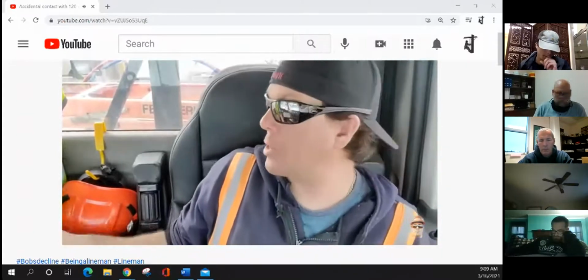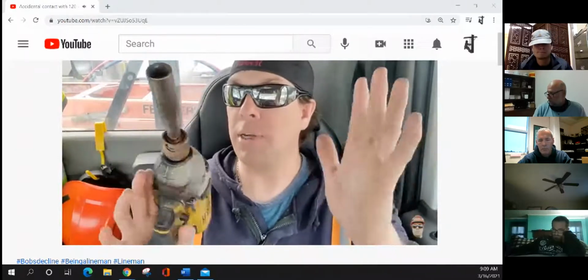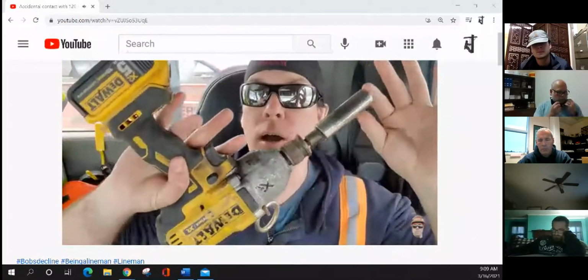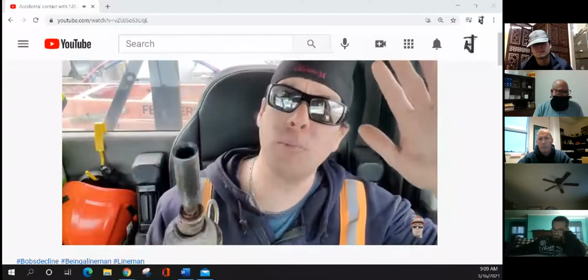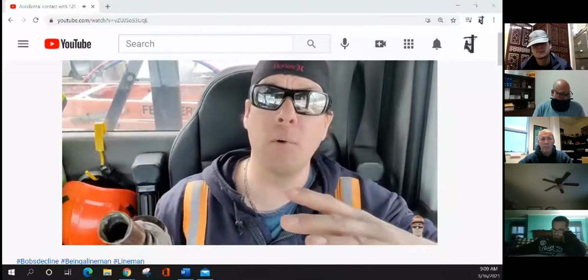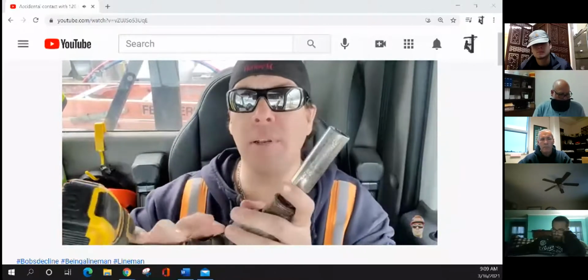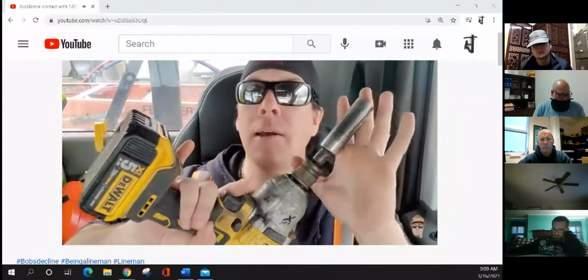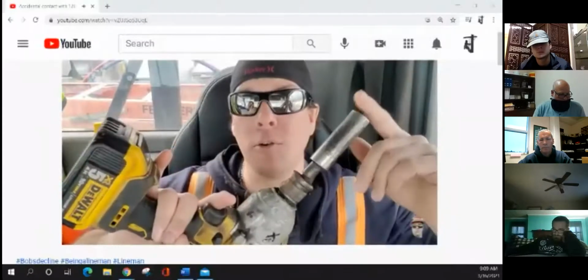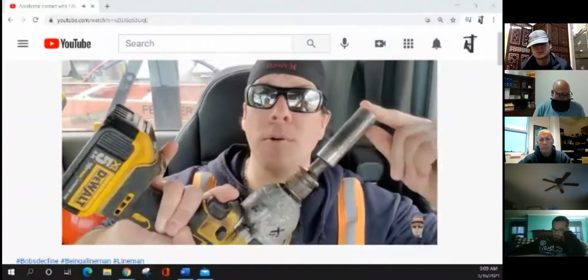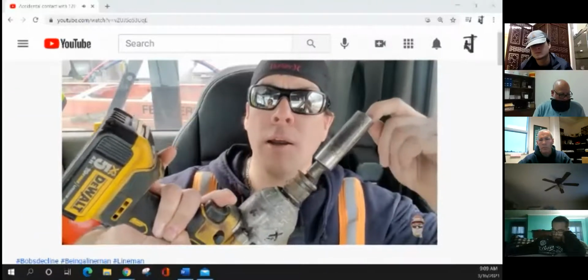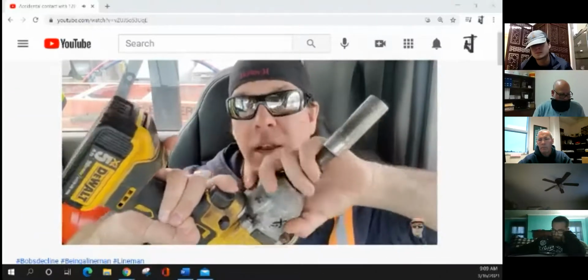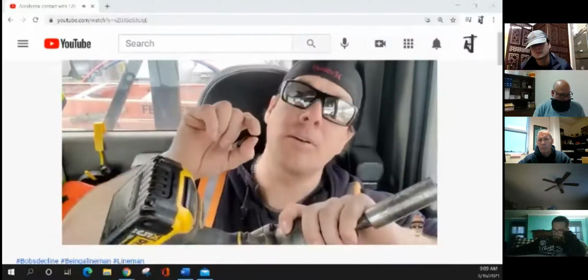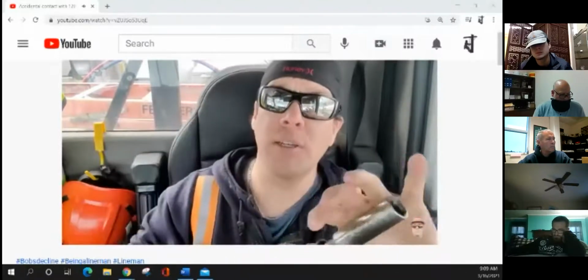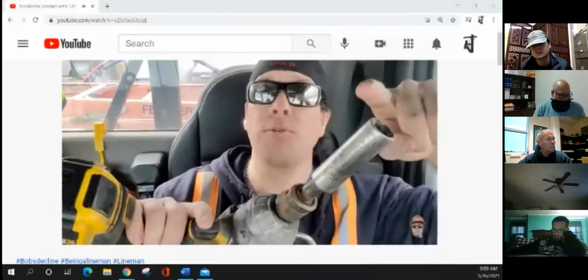The item in question was actually an impact gun. A lot of times it's normal to work on secondary while it's live. You could be tightening up a dead end unit using an impact gun, and that neutral, basically those bolts you're hooked onto, are part of the neutral wire. So if another metal part of your gun hits a phase, or if there's a crack in the insulation or a bare phase, that's going to create a path through the drill.